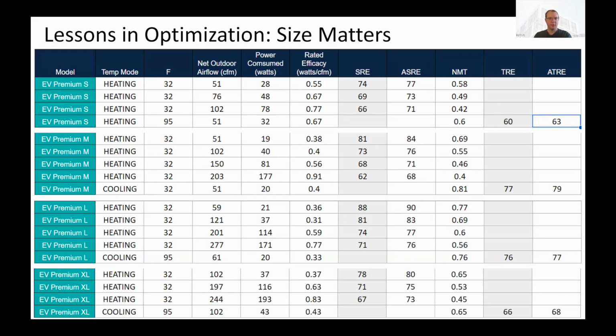Okay, so there are quite a few differences. And of course, it gets much different at the extremes. If we want to increase the ASRE further, from 77 to 84 all the way up to 90, we can use the EV Premium L to do that at roughly the same flow rates. It's even more so if we take the small and bump it to close to its maximum at 102 CFM. Follow that row across, and we see that the power is 78 watts and the apparent sensible recovery efficiency is 71%.